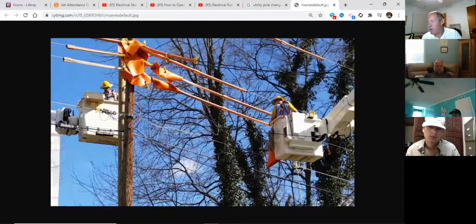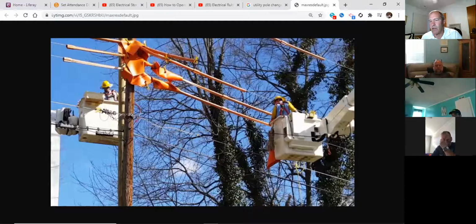You have to take into account not only the energized conductor, but what else? The de-energized one too. You have to prevent the complete path. If the guy was to accidentally come in contact with an energized conductor in the bucket, say this is 120 volts, nothing's going to happen to him. But if he comes in contact with 120 volts and the neutral, that makes a complete path. So cover up everything.